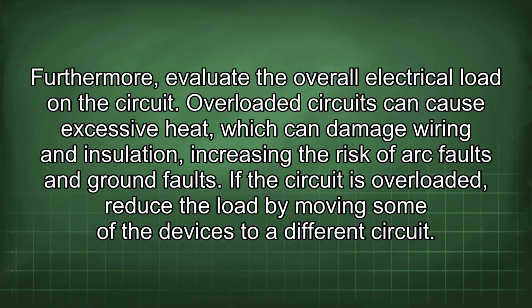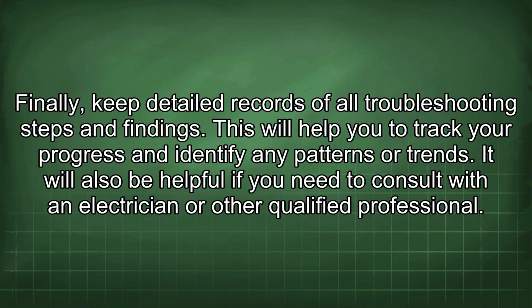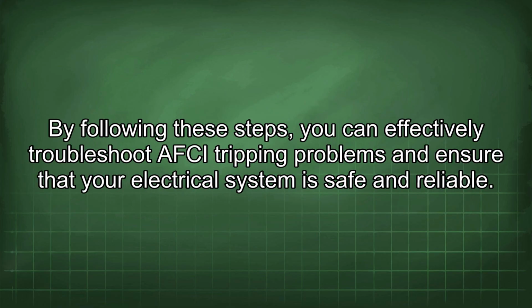Furthermore, evaluate the overall electrical load in the circuit. Overloaded circuits can cause excessive heat, which can damage wiring and insulation, increasing the risk of arc faults and ground faults. If the circuit is overloaded, reduce the load by moving some of the devices to a different circuit. Finally, keep detailed records of all troubleshooting steps and findings. This will help you to track your progress and identify any patterns or trends. It will also be helpful if you need to consult with an electrician or other qualified professional. By following these steps, you can effectively troubleshoot AFCI tripping problems and ensure that your electrical system is safe and reliable.